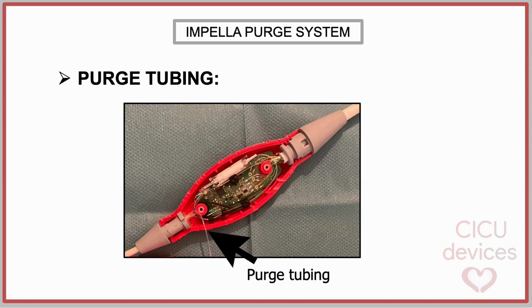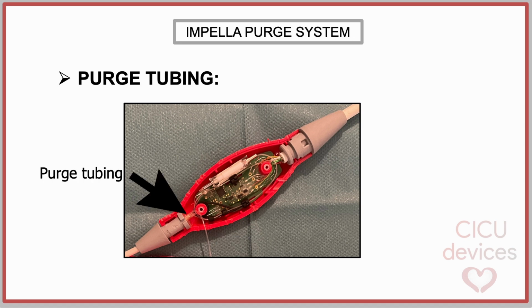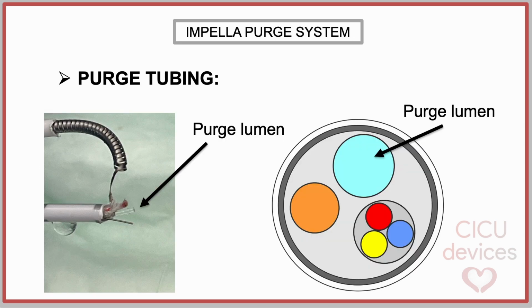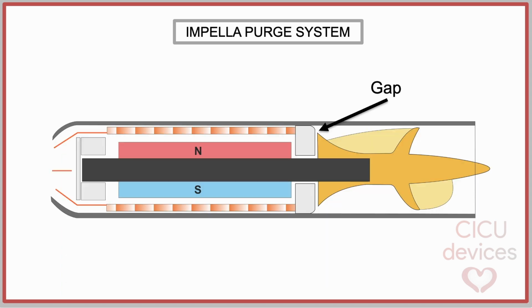From the side arm, the purge tubing enters the red hub, where it is routed toward the Impella catheter itself. Within the catheter, the purge solution travels through the internal lumen until it reaches the motor housing. Inside the motor housing, the purge fluid flows around the rotor until it reaches the gap, where it creates a barrier that prevents blood from entering the motor housing.